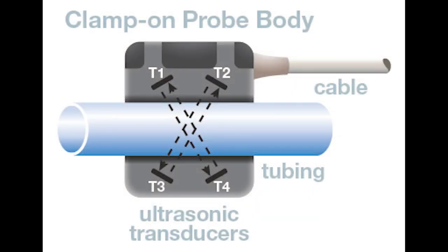Inside these sensors, two or four ultrasonic transmitters and receivers are positioned to transmit diagonally in opposite directions across a fluid to be measured.